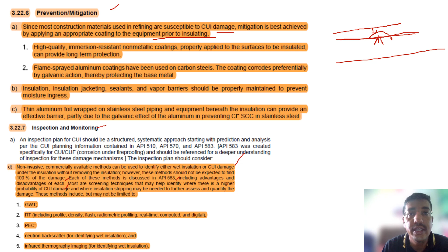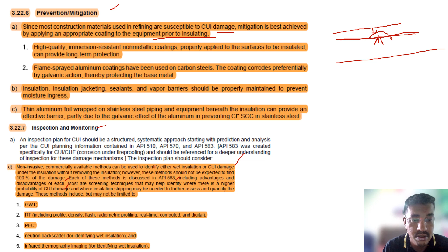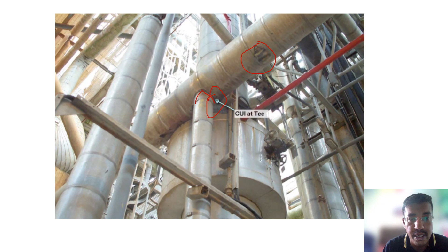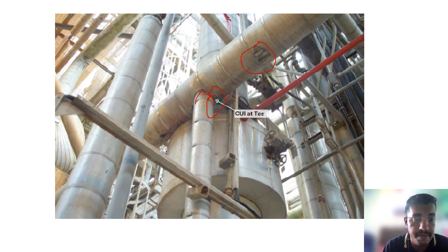There are other types of inspection, like neutron backscatter methods, but I suggest the best one is frequent visual inspection. By this method you can find out. So this is one case of corrosion under insulation that happened in one of the pipings. This was found by visual inspection, because these are the sections where it happens the most. These are the intersection areas, and all these intersection areas are where the damage can happen.